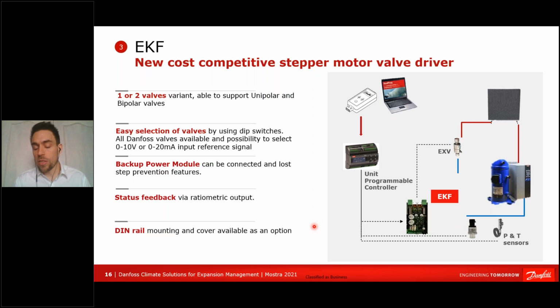The EKF was introduced because we see more and more that the unit controllers, like the MCX, do the job. Everything is centralized now in the main unit controller, and they can drive small unipolar valves. But for larger valves, they lack some power and they need some intermediate. That is why we introduced the EKF, which is a pure driver. You plug it to the MCX, the pressure and temperature sensors get back directly to the main controller, and then the main controller just sends a signal to the EKF, which amplifies it and translates it into something that can be understood by the valve.